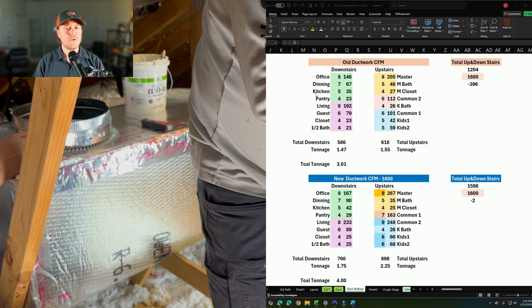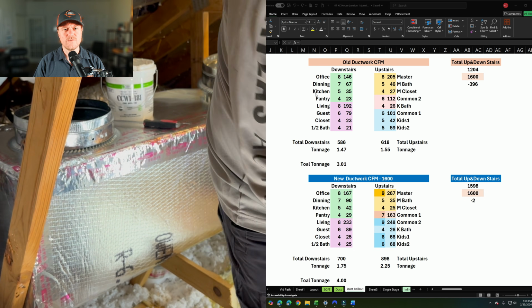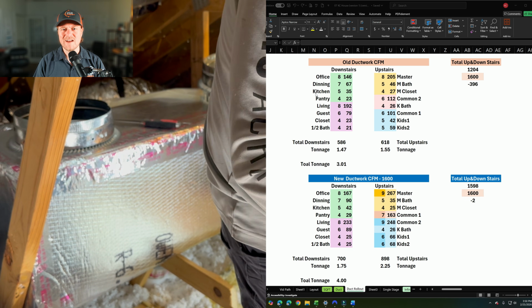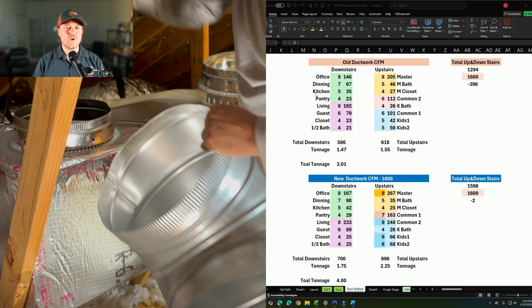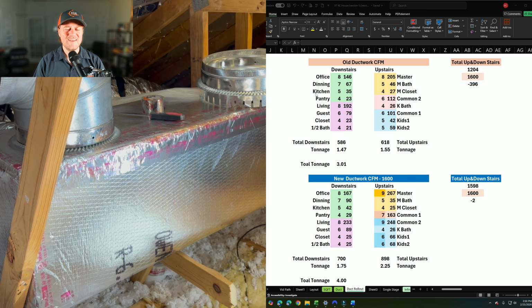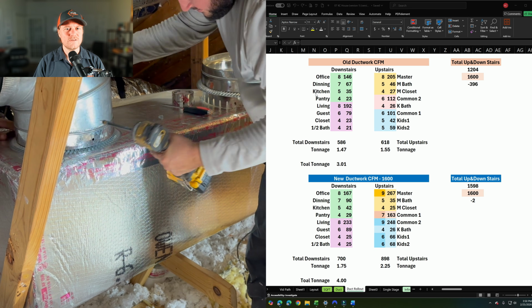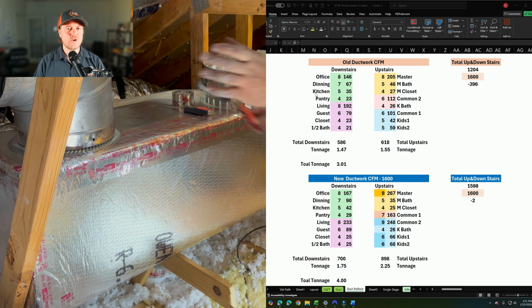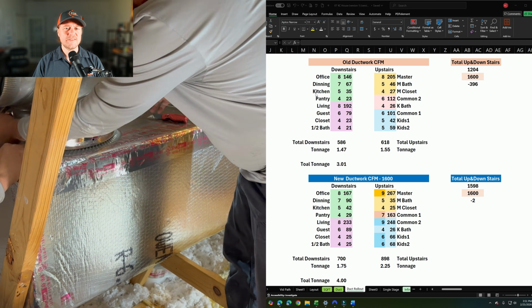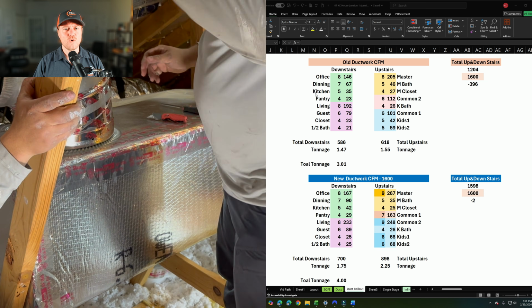There's a chance that I could have played with the AK factor a little bit more on the flow hood. It made it a tad bit more accurate, and that might have lowered the CFM readings just a smidge. However, the AK factor is really hard to get perfect. Now if I did that, it would have had a similar effect on the first 2 tests, and that's because the settings on the flow hood were the same for all 3 tests.